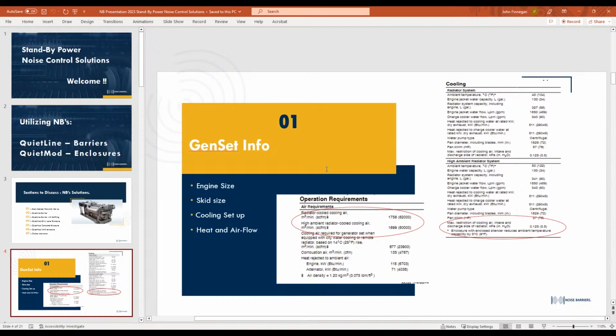Super critical, the other circle is the half inch water gauge—so half inch pressure drop max. When we're designing one of these, we really try to stay way short of that, because these prop fans on these gensets, if I'm using a connected radiator system, can't really tolerate much more than a half inch. So we try to make our entire system more in the 0.4 area, and we'll get to that.